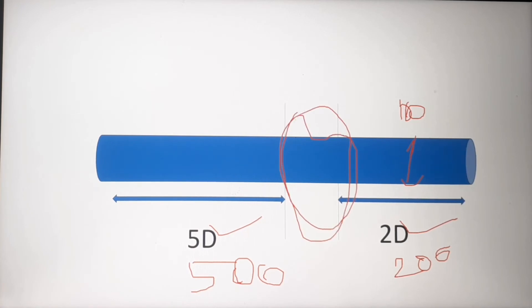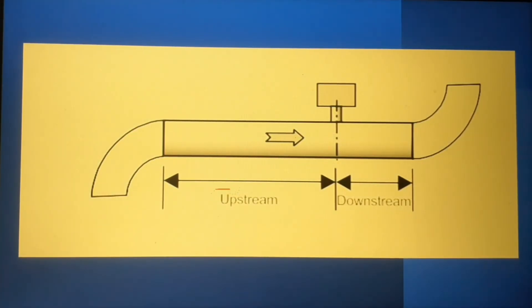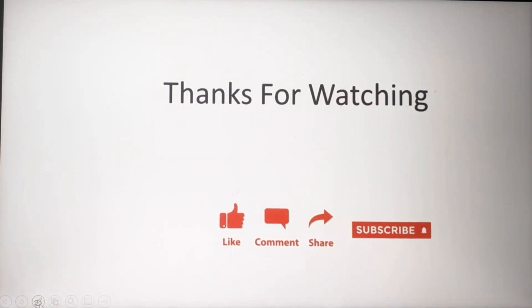When installing the flow meter or PT meter, you must follow the 5D-2D concept: 5D is the upstream side and 2D is the downstream side. Before the flow meter you need 5D of straight pipe, and after the flow meter you need 2D. Upstream means before the installation point and downstream means after it. This is typically stated in the installation manual.